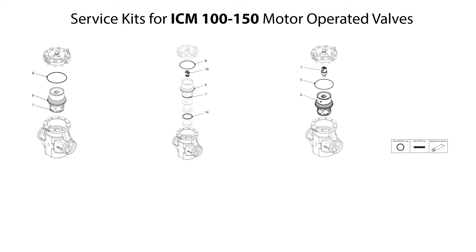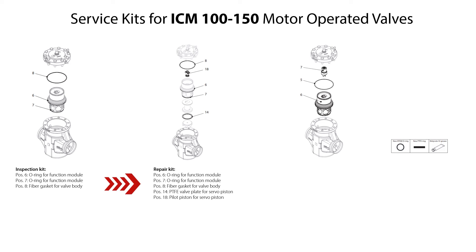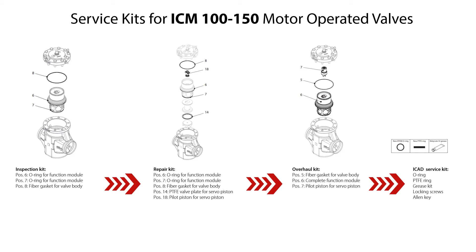You can use different available service kits to replace worn valve parts during reassembly of the ICM 100-150 motor operated valves. The available service kits are: inspection kit, which includes o-rings for the function module and fiber gasket for the valve body; repair kit, which includes o-rings for the function module, fiber gasket for the valve body, PTFE valve plate, and pilot piston for the servo piston; overhaul kit, which includes fiber gasket for the valve body, pilot piston for the servo piston, and a complete function module including o-rings and PTFE valve plate; and ICAD service kit, which includes o-ring, PTFE ring, grease kit, locking screws, and an allen key for the locking screws. Please look for spare parts details for the different ICM valve sizes in the spare parts catalog available on danfoss.com.